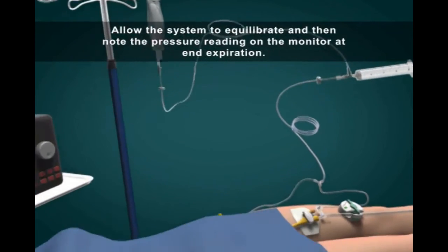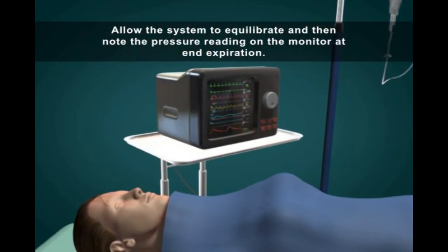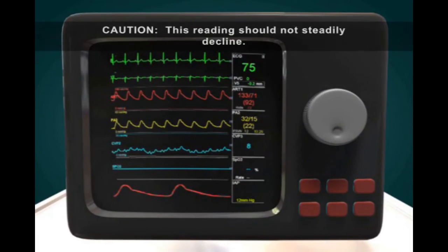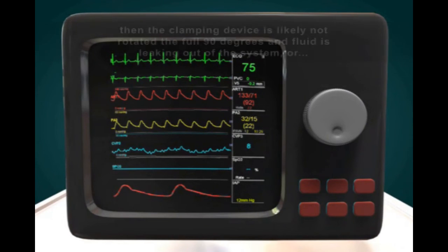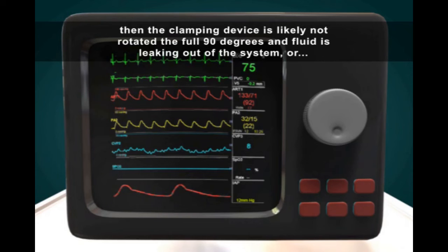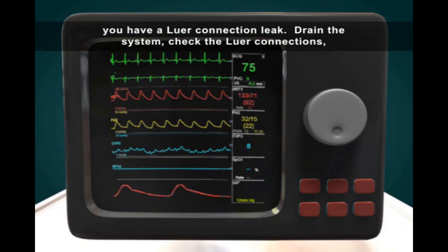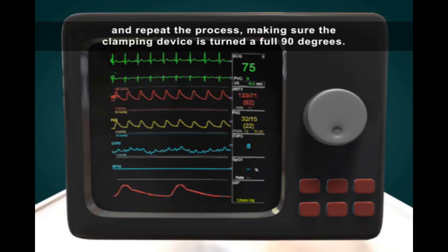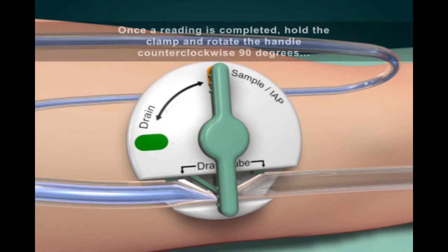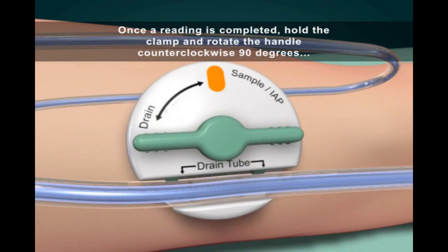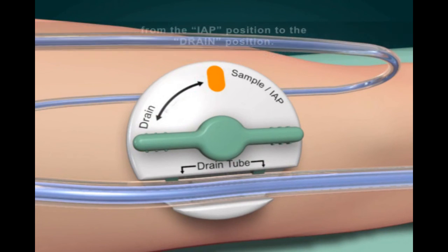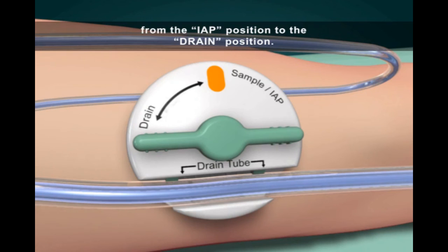Allow the system to equilibrate and then note the pressure reading on the monitor at end expiration. Caution: this reading should not steadily decline. If you find the pressure reading drifts down, then the clamping device is likely not rotated the full 90 degrees and fluid is leaking out of the system, or you have a luer connection leak. Drain the system, check the luer connections, and repeat the process, making sure the clamping device is turned a full 90 degrees. Once a reading is completed, hold the clamp and rotate the handle counterclockwise 90 degrees from the IAP position to the drain position.